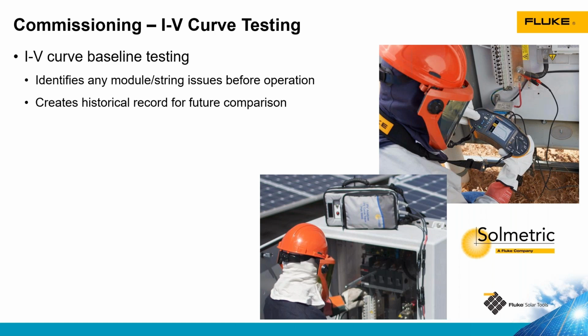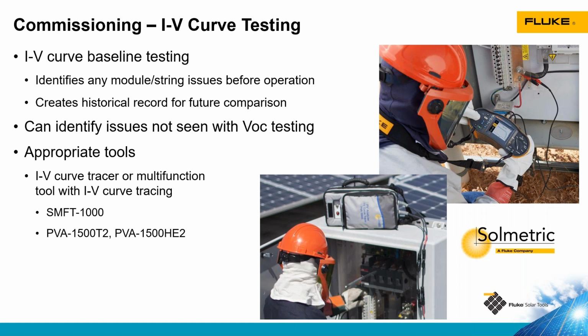At commissioning, if we're doing an IV curve test of our entire system, we can create a historic record so we know everything was working properly when we started the system, and if there are any changes in the future, we can always refer back to this test data. At Fluke, we have 3 IV curve testers. The SMFT 1000 is capable of testing up to 1,000 volts and 20 amps. The 2 PVA products, the 1500 T2 and 1500 HE2, can both measure up to 1,500 volts and 30 amps.